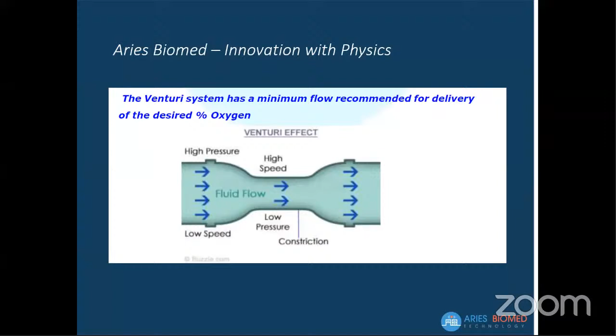And the fourth thing is not only to generate high flow, but also to blend oxygen and to generate CPAP pressure. In a basic turbine-based system, it cannot do CPAP pressure on a high flow device. So we came out with the Venturi adapter. It's a Venturi capsule we developed with a 5-axis CNC. Basically, it uses the Venturi. You physics students must be very familiar with what a Venturi is, right? A Venturi is basically an air amplification system, which makes any fluid or air, when it gets into high pressure, get multiplied with respect to the flow, and it also sucks air from the atmosphere and blends it. Okay, so this is the system we conceptualized and presented to the Indian government.